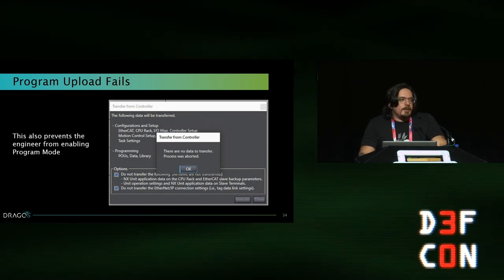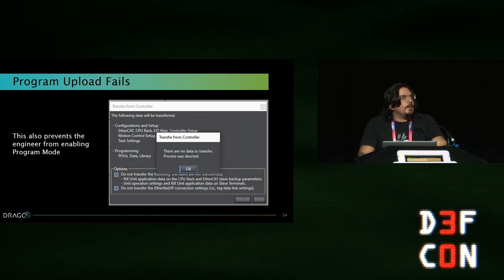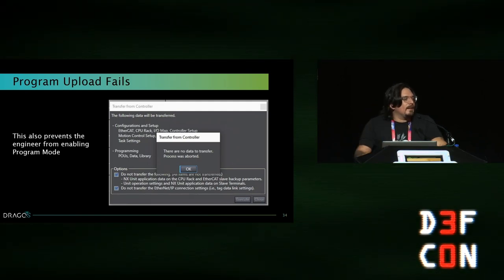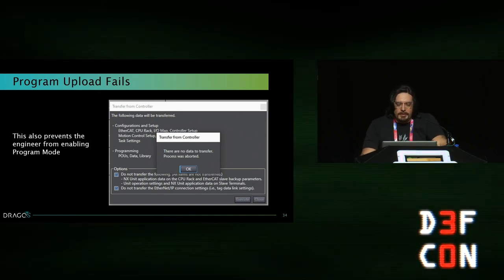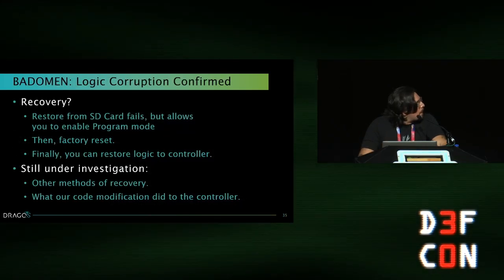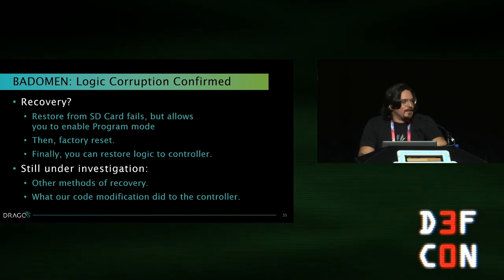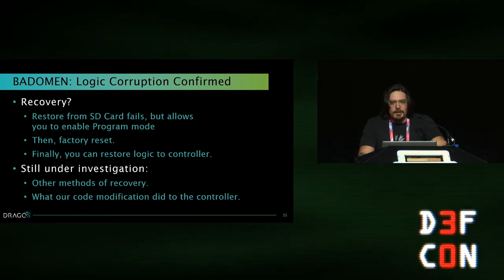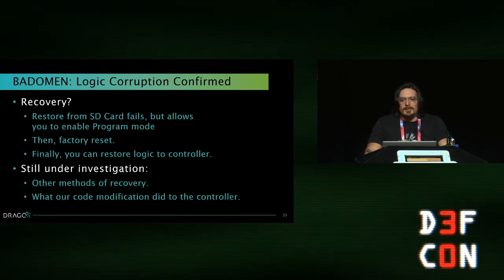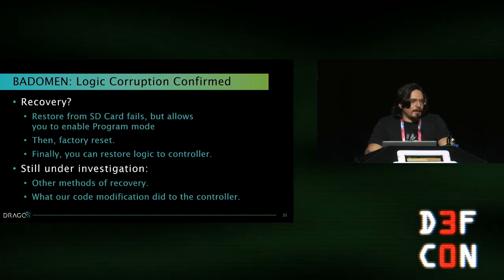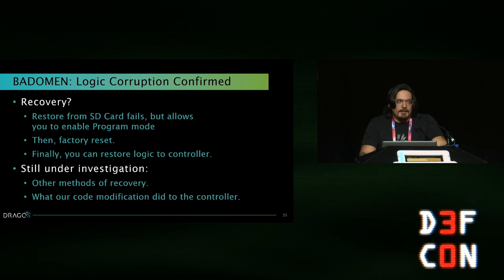There's some versioning where the EWS says there's nothing to pull back — everything is still the same. It also prevents you from enabling program mode, so you can't recover normally. We tried restoring from an SD card, which failed but for some reason allows you to set program mode again. Then a factory reset, then restore logic to the controller. Sounds like a medium pain, but imagine a plant engineer dealing with this — that's the rest of his day, probably a call to the vendor, wait time, and significant downtime. Depending on what's being processed, that's a lot of money.